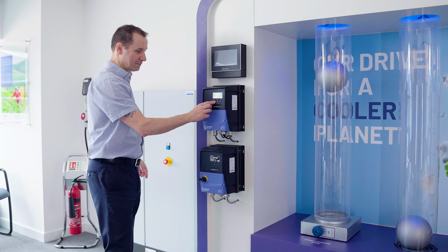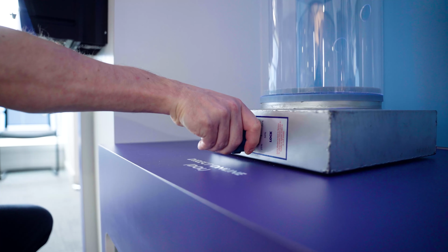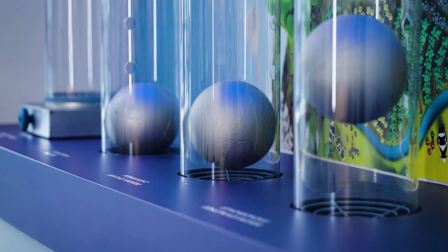Within the demonstration unit that we have here, we have one fan that's connected directly online, and that's using a traditional damper. So it's a mechanical means of reducing the airflow, which we know historically these are the least efficient way to control air, but it gives us a baseline to be able to demonstrate the starting point of the application.